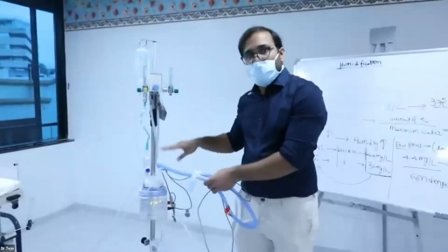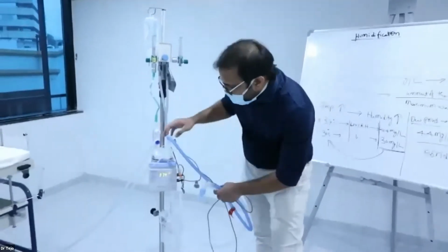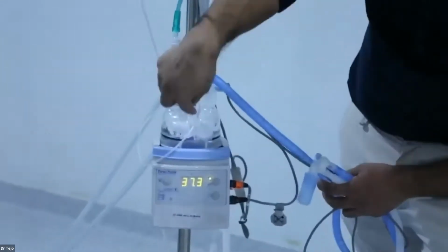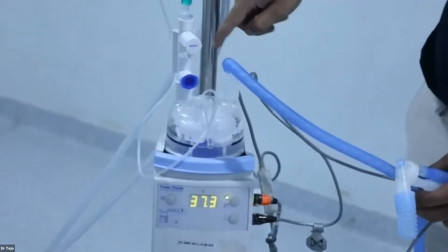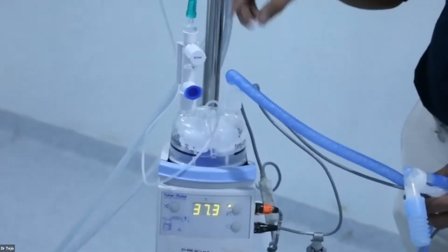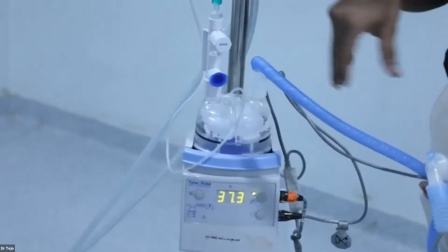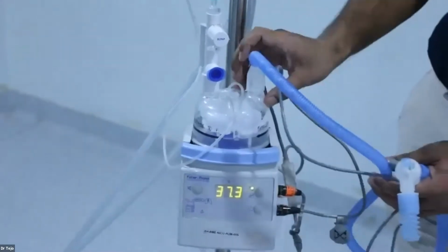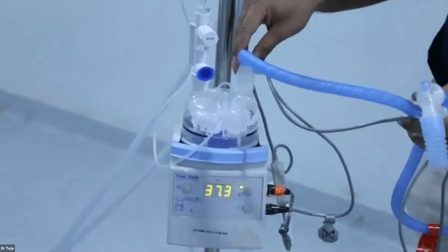You can come down. So when you see this humidification chamber, it has a corrugated inside. It has serrations, turns and all. So this is corrugated, so the surface area traveled by the air will be increased. It will have proper humidification by increasing the surface area, without requiring much space because of the corrugations. And then after the air enters and is properly humidified, it exits through this chamber port.